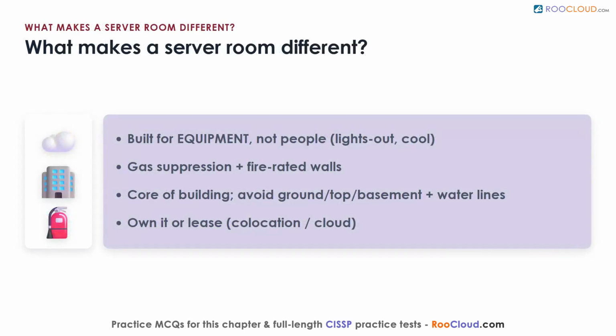What makes a server room different from an ordinary room? It is built for the equipment, not for people. A server room is a restricted, enclosed space, often run lights out and kept cool, because comfort for workers is not the goal. It may include gas-based fire suppression and walls rated to resist fire for a set period. Place it at the core of the building and avoid the ground floor, top floor, and basement, along with anywhere near water, gas, or sewage lines that could leak or flood.